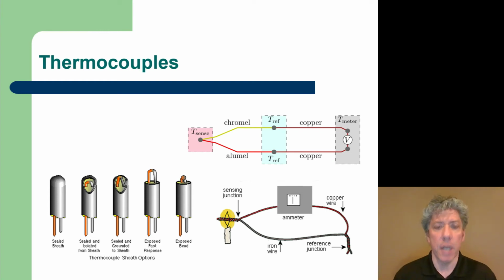There is a cutaway for the next image that is showing a sealed thermocouple that is also isolated from the sheath. So you'd want some type of material filling in there in order to transfer thermal energy from the sheath to the thermocouple, but electrically they would be isolated from one another because often you don't want the thermocouple wire, which is part of an electrical circuit, to be grounded. It's very common that the sheath itself is made of metal and is grounded. So this further degrades the time performance, or the amount of time that it takes for the thermocouple to respond.